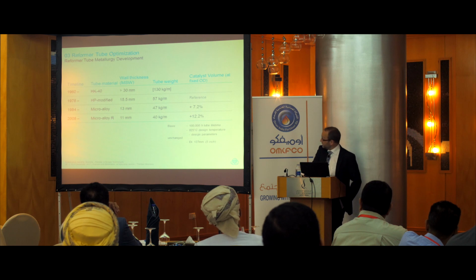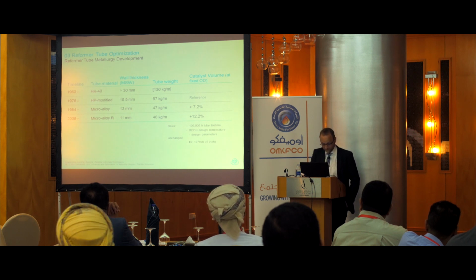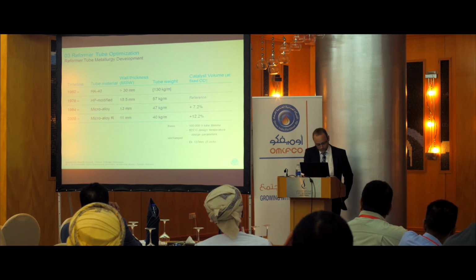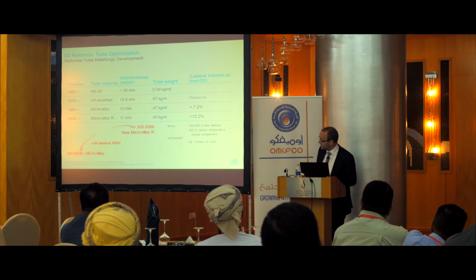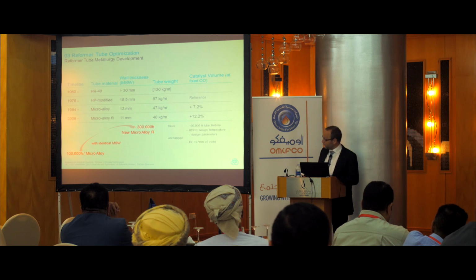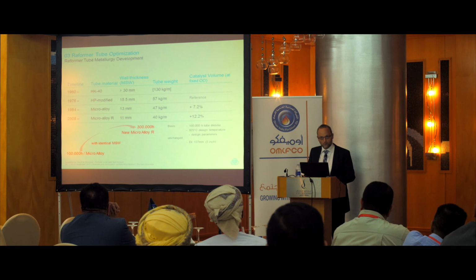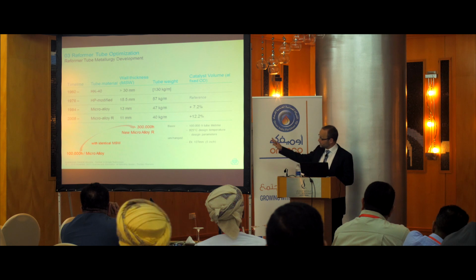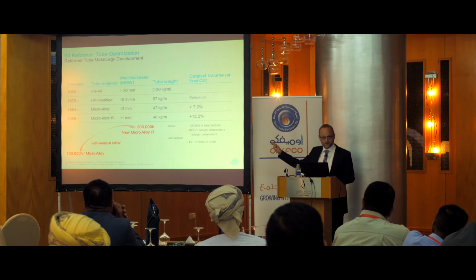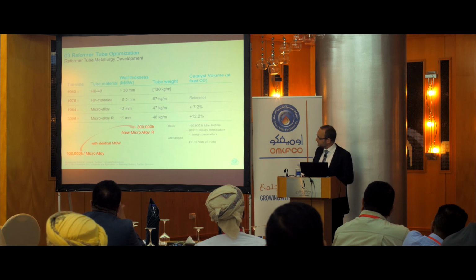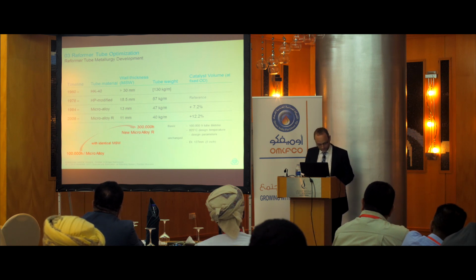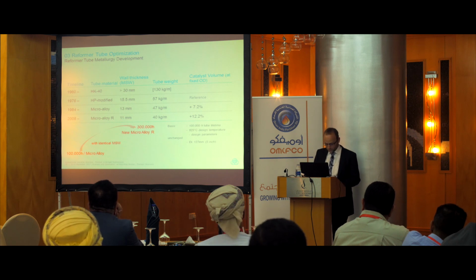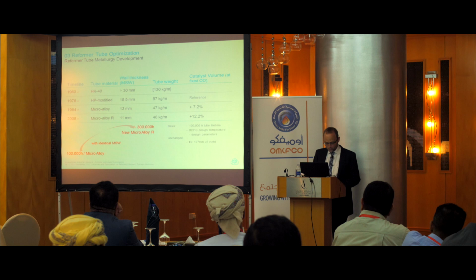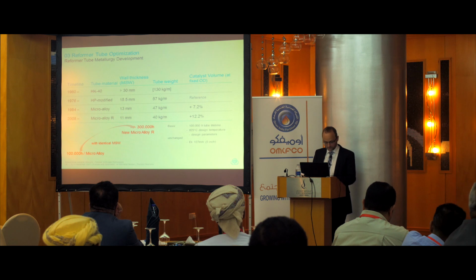Last but not least, the lifetime of the tubes can be increased. When we keep the same minimum sound wall thickness, in this example, if you increase from microalloy to the latest version, you can around triple the lifetime of the reformer tubes. Of course, that's a bit theoretical value, because Larson-Miller parameters are not that exact, but that's the number we are talking about. To summarize, the latest developments in tube metallurgy open many options for the operator for cost savings, revamps, or plant expansions.